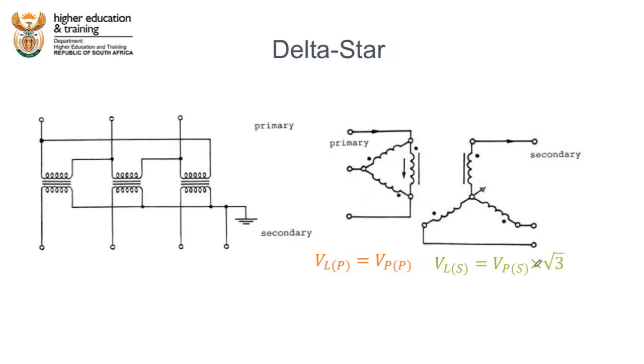The fourth configuration is to connect the transformer as a delta-star. The primary is connected in a delta configuration and the secondary in a star configuration. For the delta primary, line voltage equals phase voltage. For the star secondary, line voltage equals phase voltage multiplied by the square root of three. On the primary side the end of each coil connects to the start of the next, and on the secondary side the ends of all three coils connect to the same point — from which we very often take an earth or neutral.